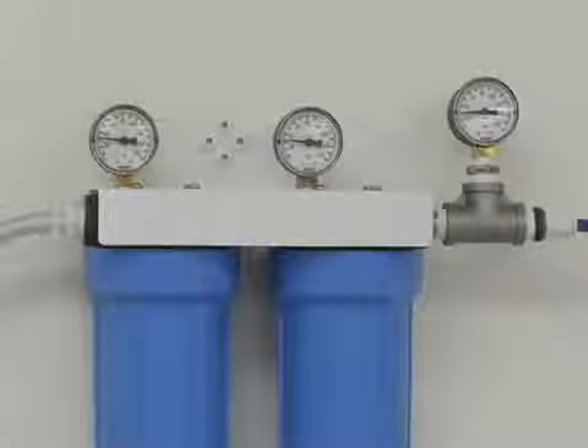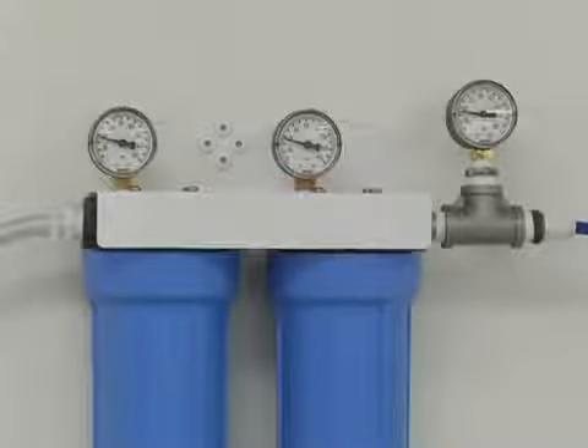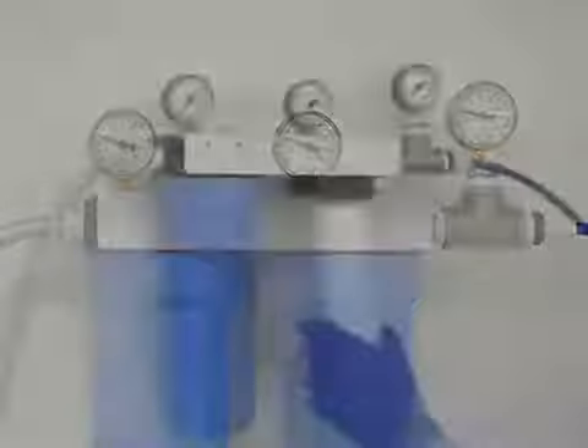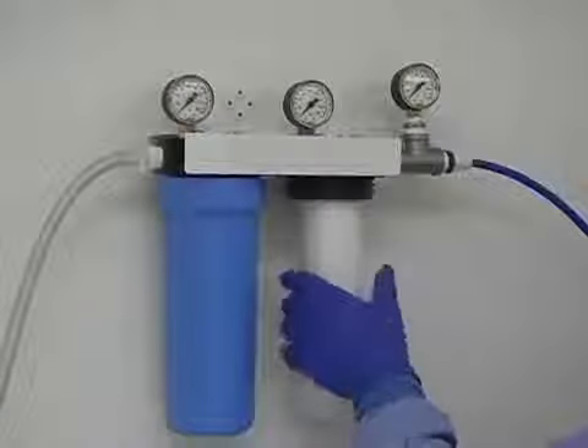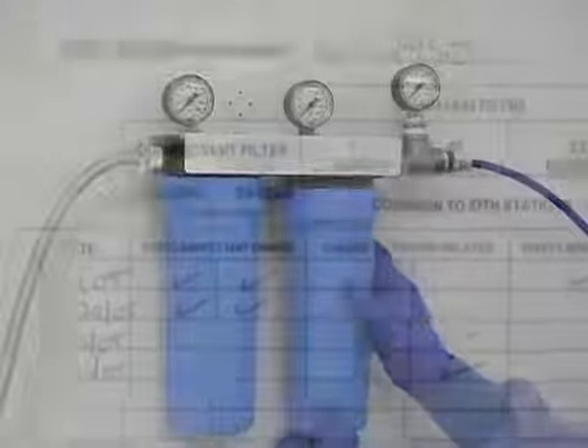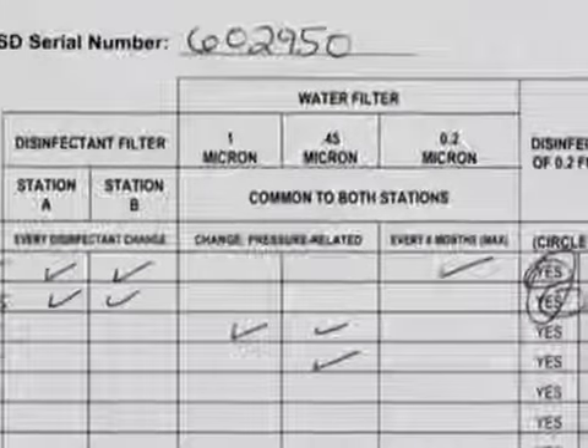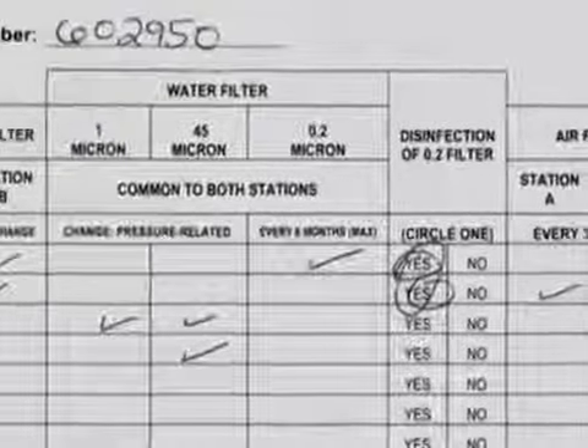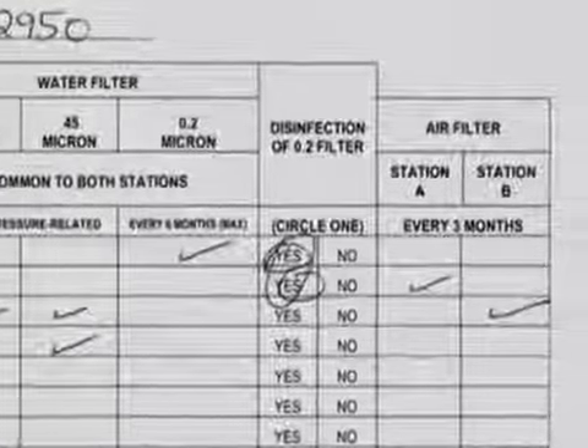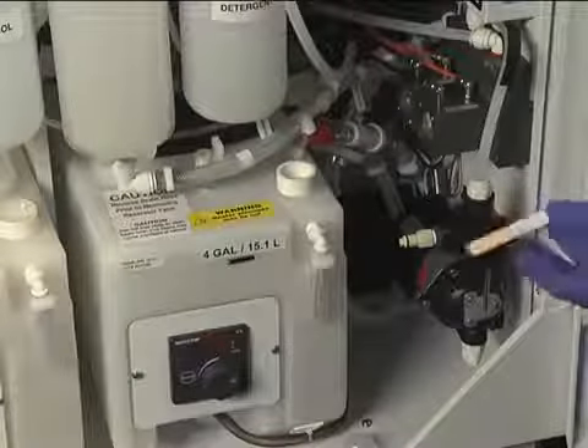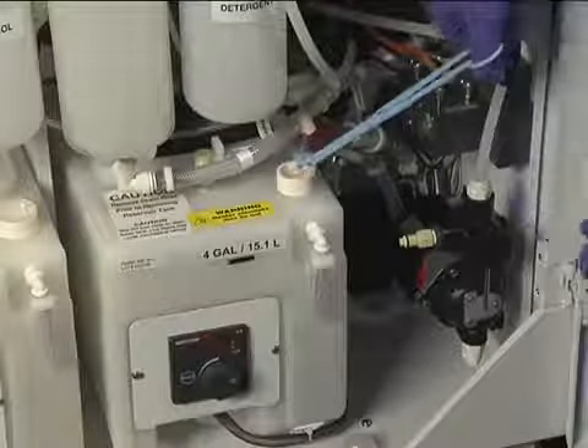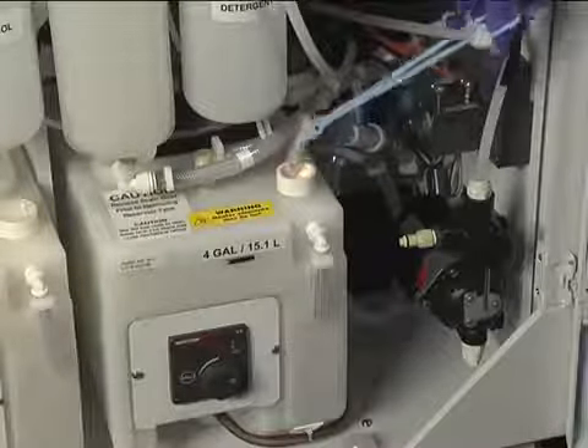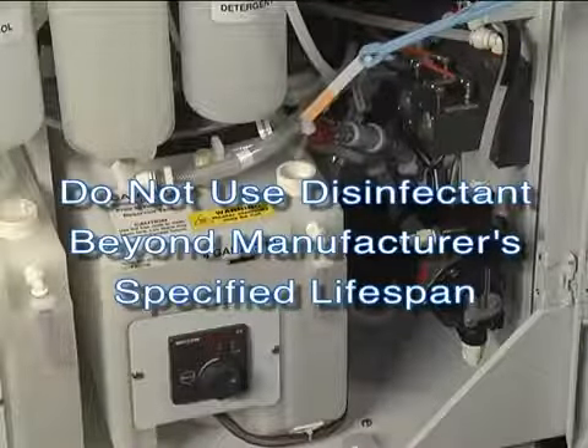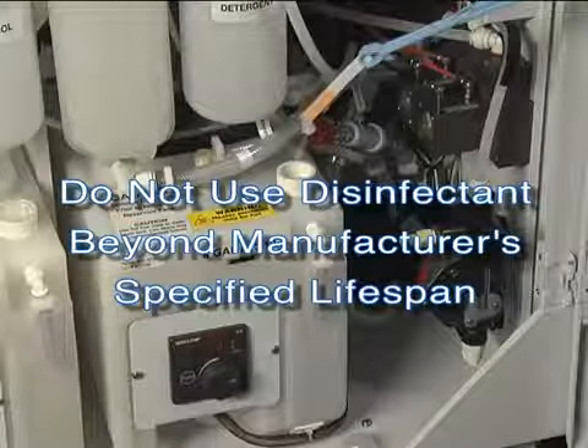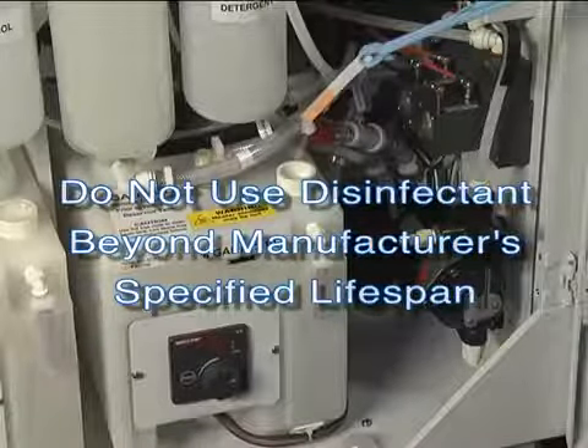Check the external pre-filters. Inspect the gauges for noticeable water pressure drops and replace the appropriate filter as necessary to maintain 40 psi. Check when the disinfectant and related filters were last changed. If the disinfectant is within its usable lifespan, test it to ensure it is at least at the minimum effective concentration specified in the directions for use of the disinfectant. Regardless of the results of the MEC check, the disinfectant must be discarded once it has passed the lifespan indicated in the manufacturer's directions for use.